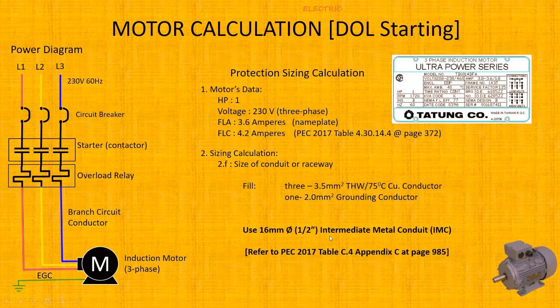Using PEC Table C.4 and the conduit fill calculation, with a total conduit fill area of 4.75 cm², the conduit equivalent is 16.5mm. Therefore, use a 1/2-inch IMC conduit, though PVC conduit may also be used depending on the installation type.